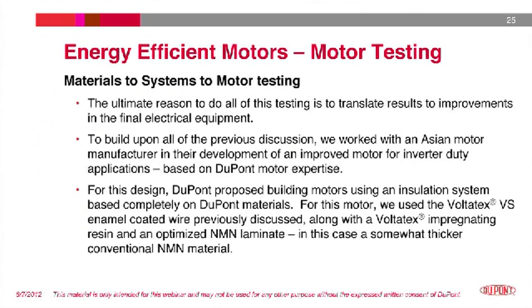With these positive results from the motorette testing, we then tested three different motor designs as complete motors using the same test protocol. In this test, one of the motors was a standard industrial motor, the second was a motor designed for inverter duty applications, and the third was a motor designed by an Asian motor manufacturer with the assistance of DuPont engineers. For this motor, DuPont proposed manufacturing the motor based completely on DuPont materials, with Voltatex VS wire enamel, DuPont Voltatex impregnating resin, as well as an improved NMN laminate versus that used in the other two motors.